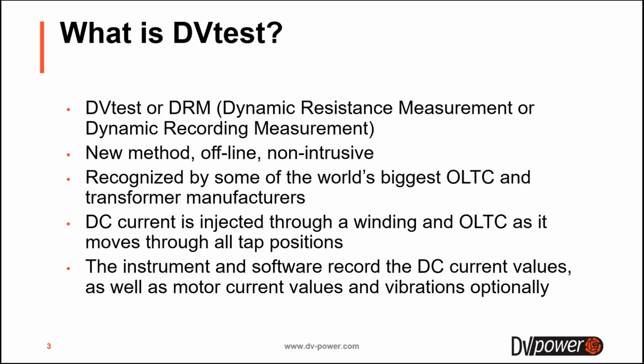So how does this method work? It works in the way that DC current is injected through a winding and therefore through the on-load tap changer. And the on-load tap changer is being operated or moved through all tap positions. The test instrument and the appropriate software record the DC current values, and optionally they can also measure or record the on-load tap changer motor current values and the vibrations of the on-load tap changer.